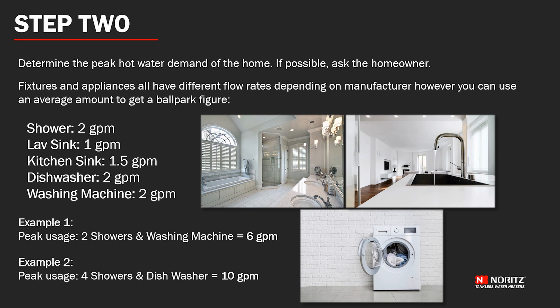Example 1 shows a fairly average use of two showers and a washing machine at the same time, totaling 6 gallons per minute. While example 2 shows a rather large peak demand of 4 showers and a dishwasher, totaling 10 gallons per minute.